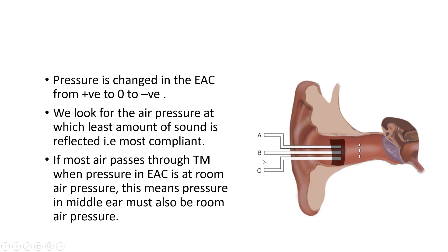When we apply positive pressure in tympanometry, we first apply positive pressure through chamber B — the tympanic membrane goes towards the medial side. This creates a very tense, tight tympanic membrane and most of the sound is reflected back, recorded in chamber C, the microphone. Now we decrease the pressure from positive towards 0, and when it comes back to its original position, that's when the tympanic membrane is most compliant. It allows most of the sound waves to be transmitted to the middle and inner ear, and the least amount of sound waves is reflected back and recorded by the microphone.